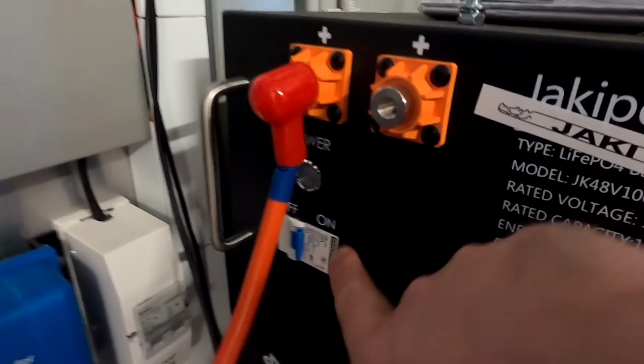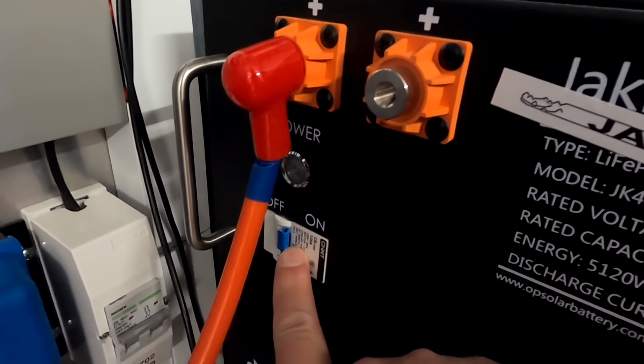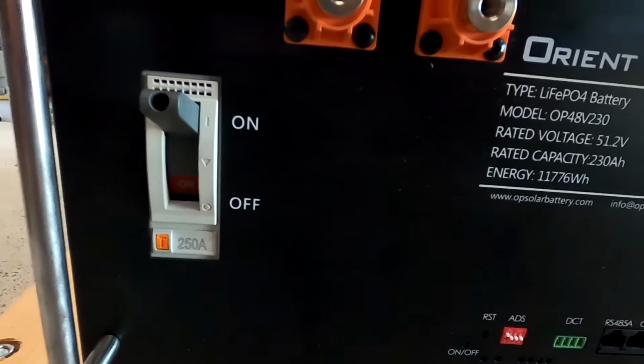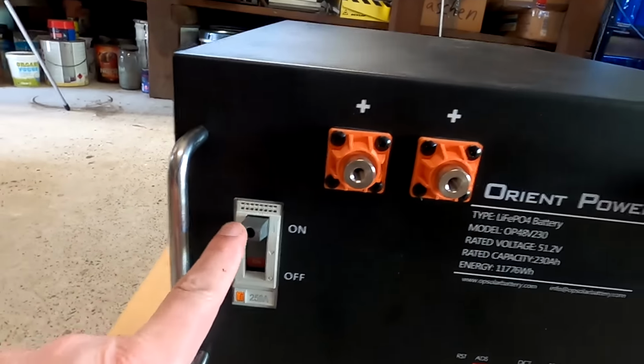The smaller Jaki with 100 ampere hours also has a circuit breaker where you can manually turn off the whole battery, mechanically disconnecting it. It's not just a soft button which turns off the BMS, it's a hardware button that physically disconnects your positive from the rest of the system. This is already a big plus we haven't seen in any battery other than the Jaki batteries.